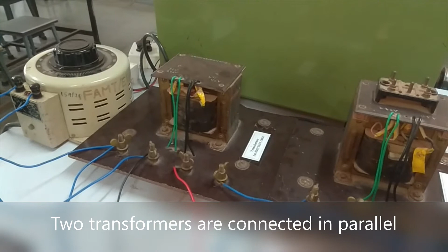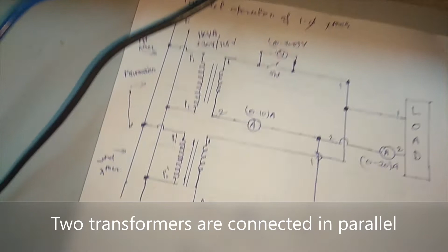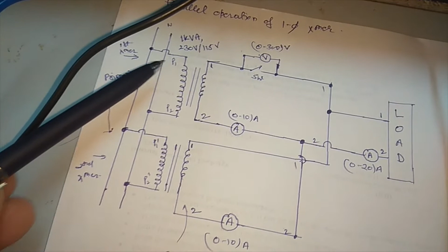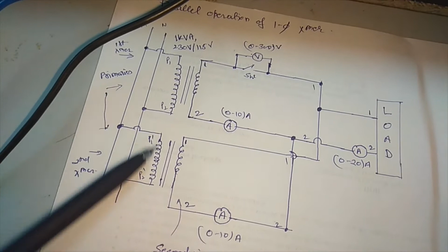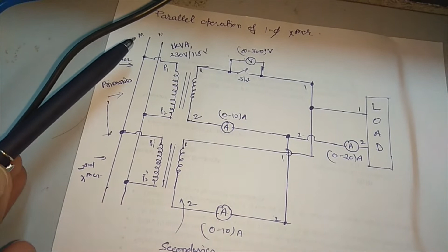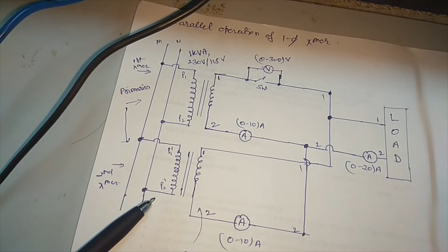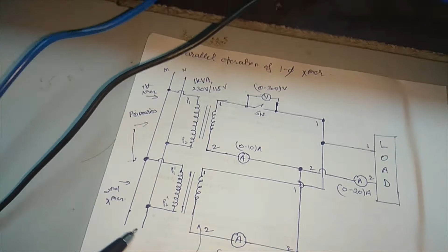Considering the circuit diagram, we have already connected the transformers, so let's check whether the connections are correct. We can see the primary of the first transformer is marked P1, P2, and the second transformer P1 dash, P2 dash. P1 and P1 dash are connected together and then connected to one supply terminal, and P2 and P2 dash of both transformers are connected together and connected to the other supply.